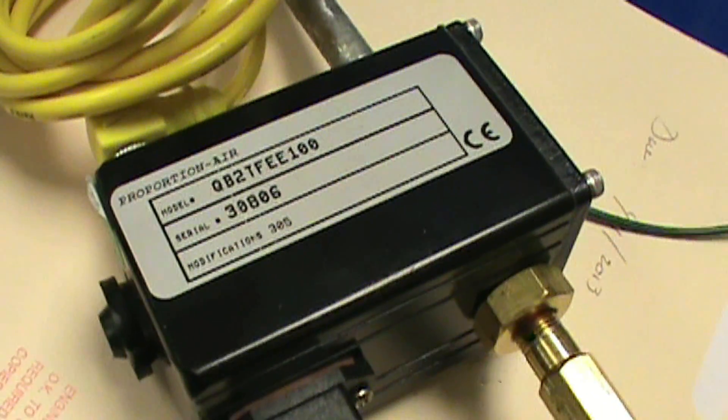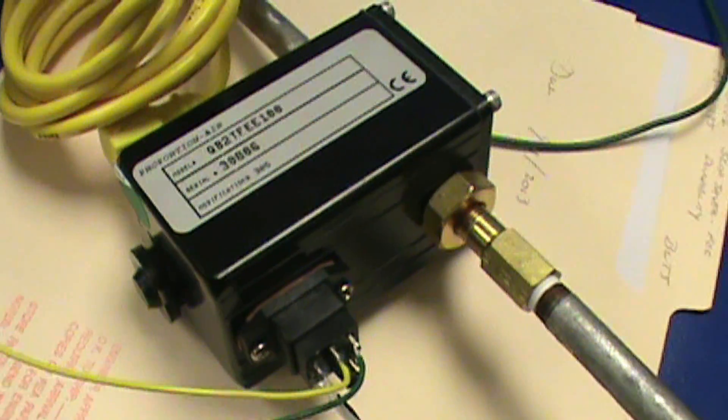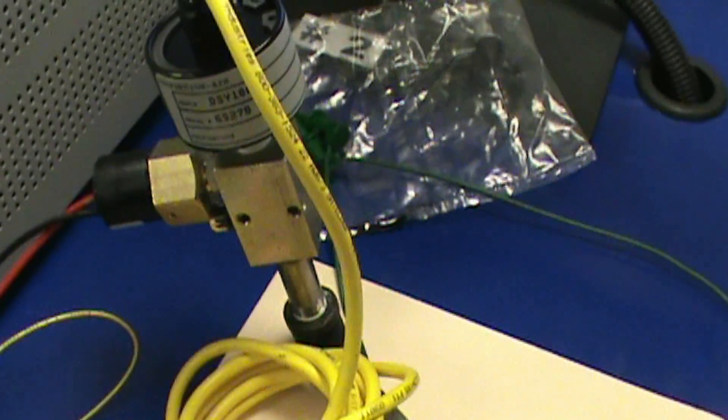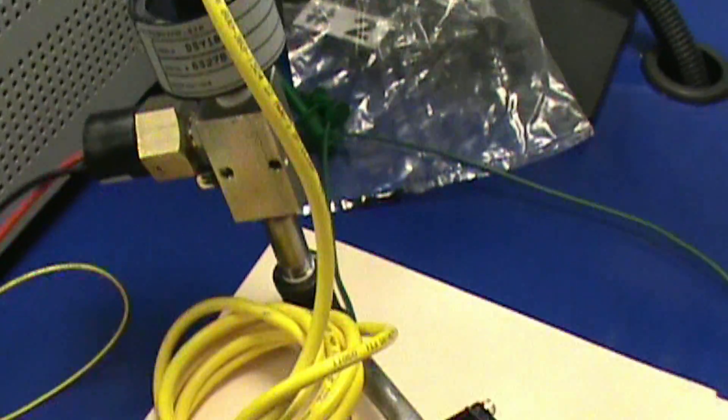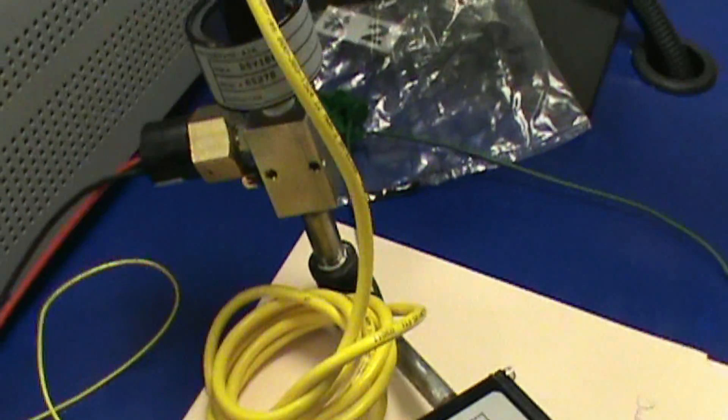The heart of our setup is this little proportional air controller. It takes a 0-10 volt ramp which comes from our National Instruments equipment and generates a 0 to 100 psi output. It has an accompanying pressure transducer that it reads and close loops on, so you get very precise control.